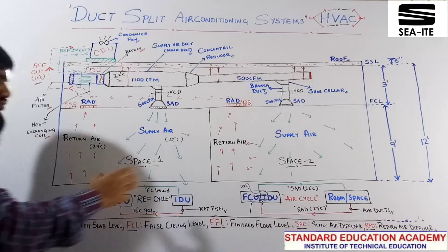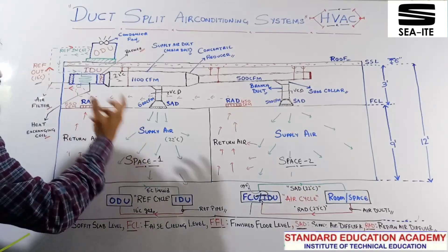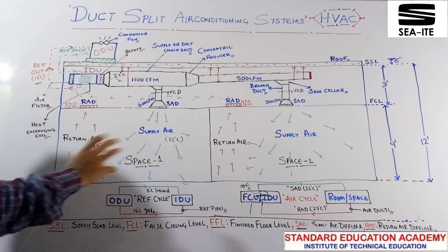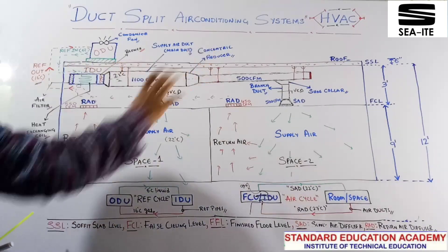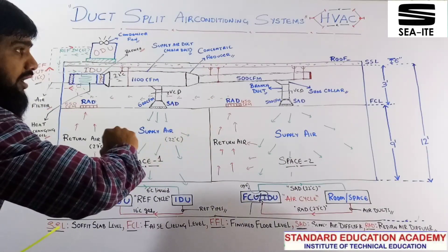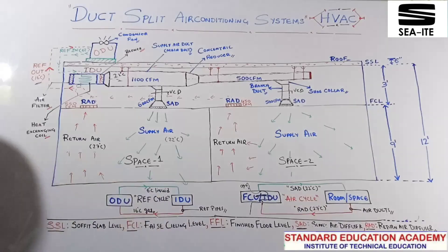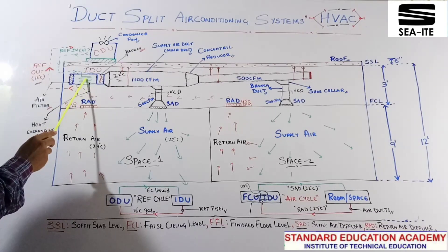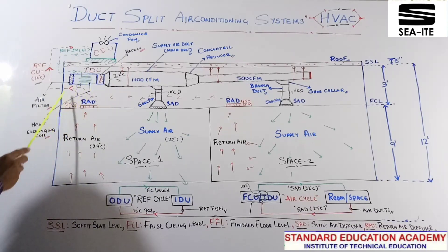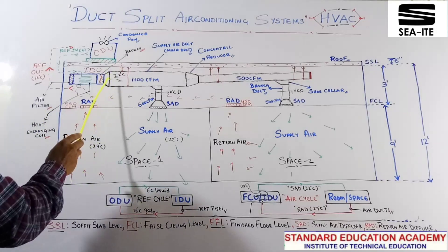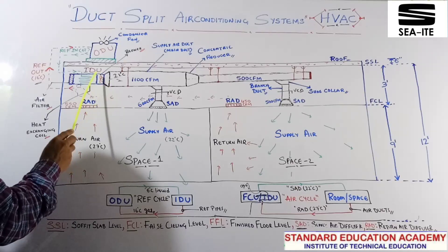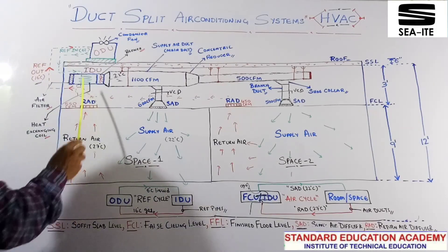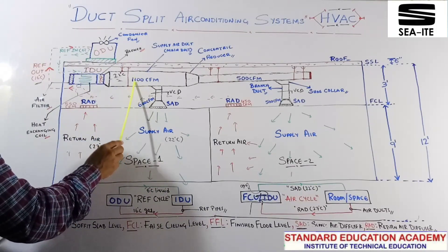This is the way these two cycles work together to give you a proper required temperature. Now I have explained both the cycles — refrigerant cycle and air cycle. Let's explain the different components and walk through the total sectional view I have drawn here. This is the outdoor unit with the condenser fan. This is your indoor unit. These are the heat exchanging coils, blower, filter section with dampers. Here I have given a mouthpiece attached such that a duct can be easily fixed to this IDU.